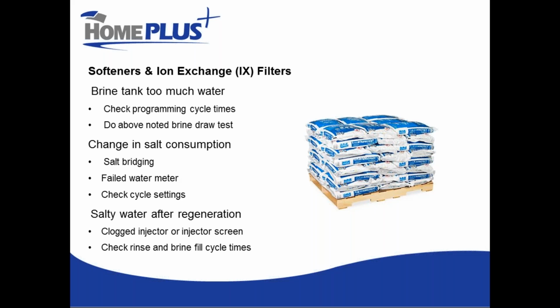Changes in salt consumption are also good indicators that you have a problem. Sometimes a change in salt consumption will be just strictly tied to a change in water use within your facility. That's normal, but if your water use is as it usually is and you're seeing increased or decreased salt consumption, you should proactively start looking to see why that's occurring and hopefully address something before it becomes a bigger problem.